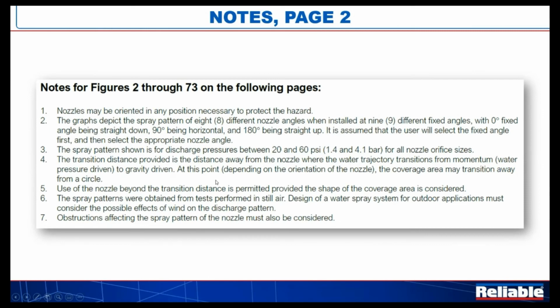You can use it beyond the transition distance. This is just a reference point. So don't think that, hey, I can't go beyond 3.5 feet, because you can. You just need to look at what the water's doing at that point. Again, number 6, these spray patterns were obtained from tests performed in still air. So you must consider the effects of wind and then obstructions. You are not going to be able to go to NFPA 15 and find obstruction tables like you do in NFPA 13. It's just not going to happen. So you need to look at those individually and do some engineering analysis on obstructions.